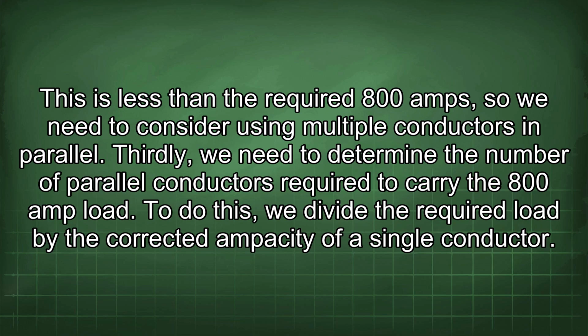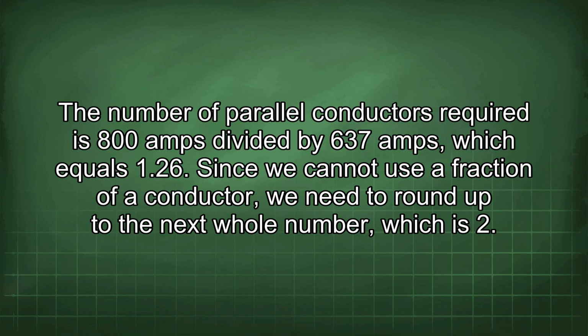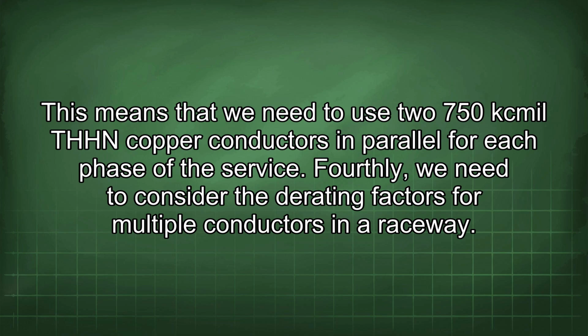Thirdly, we need to determine the number of parallel conductors required to carry the 800 amp load. To do this, we divide the required load by the corrected ampacity of a single conductor. The number of parallel conductors required is 800 amps divided by 637 amps, which equals 1.26. Since we cannot use a fraction of a conductor, we need to round up to the next whole number, which is 2. This means that we need to use two 750 kcmil THHN copper conductors in parallel for each phase of the service. Fourthly, we need to consider the derating factors for multiple conductors in a raceway.